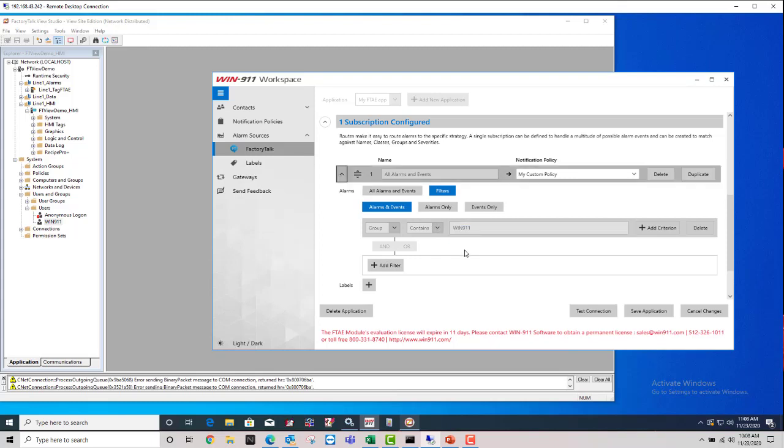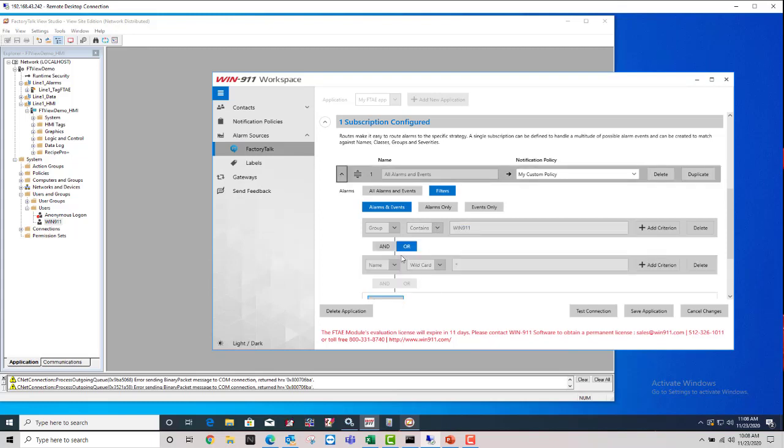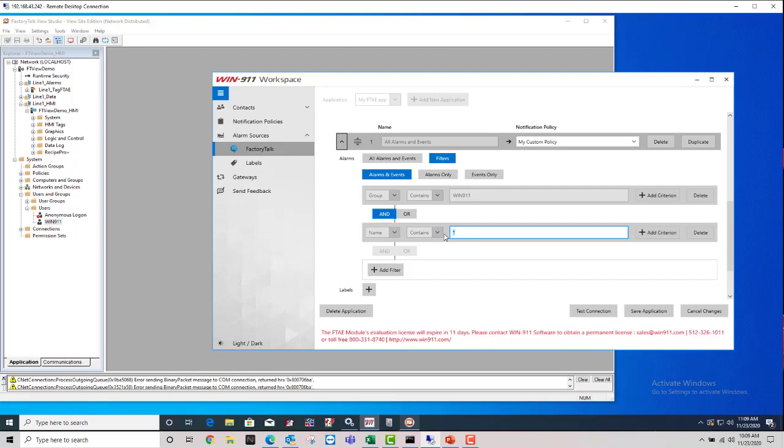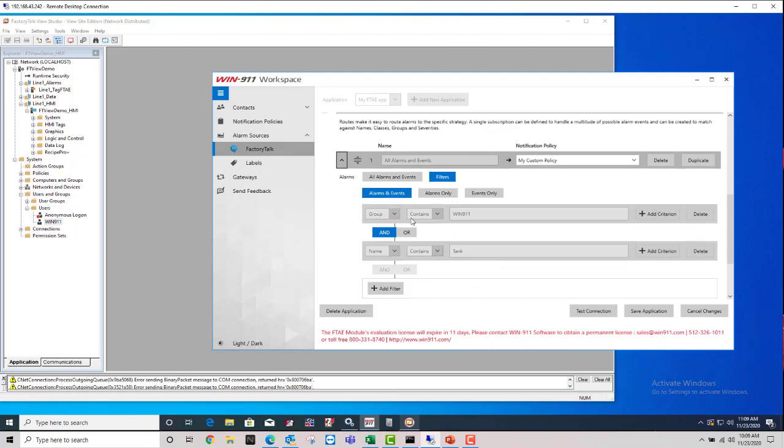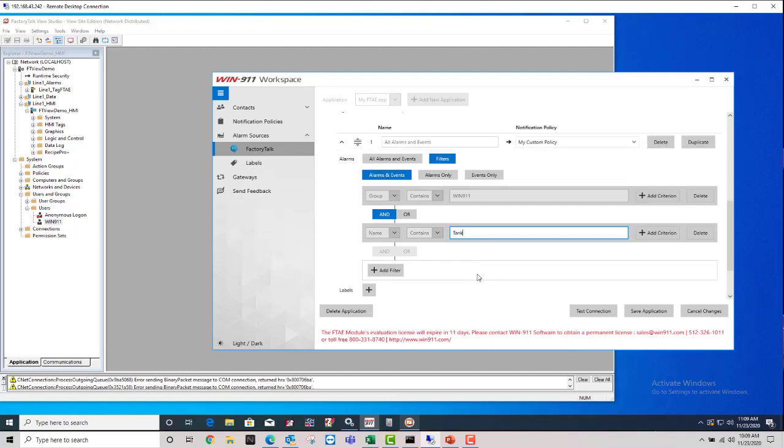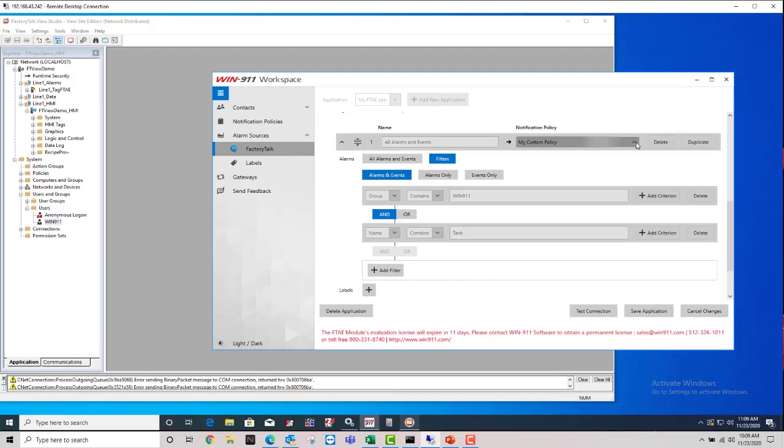Now, you can make these pretty complex and continue to add filters and use these and and or. Make them as complex as needed. The group contains Win911 and the name contains tank, for example. This is now a filter that as long as the alarms come from the group Win911 and the alarm name contains the word tank, it'll grab those alarms. And when it grabs those alarms, matches these filter criteria, it's sending it to your notification policy you selected right up here.